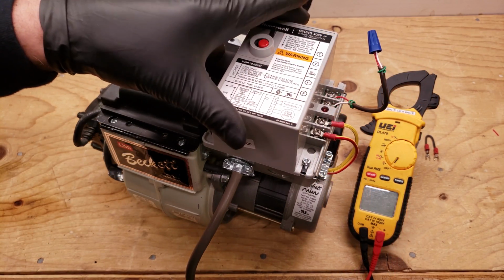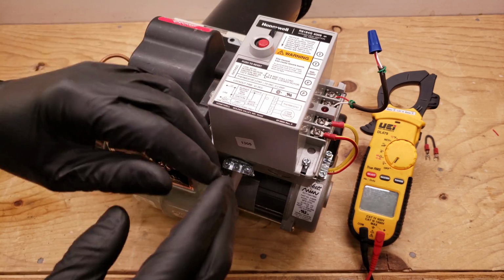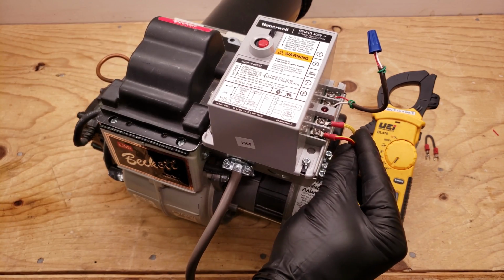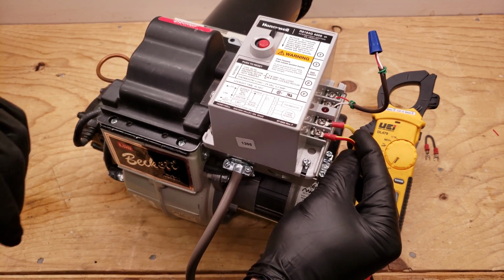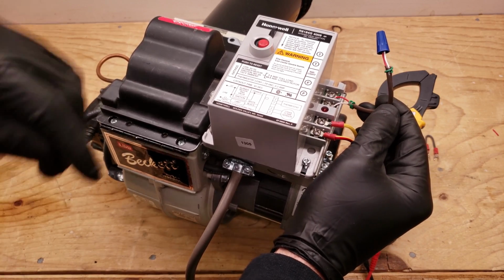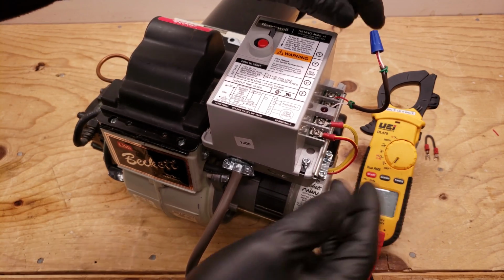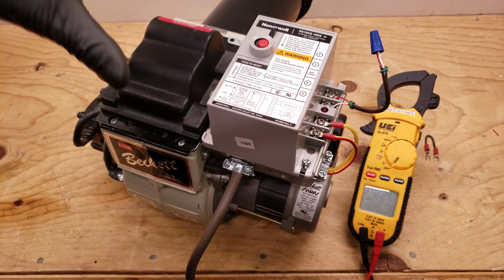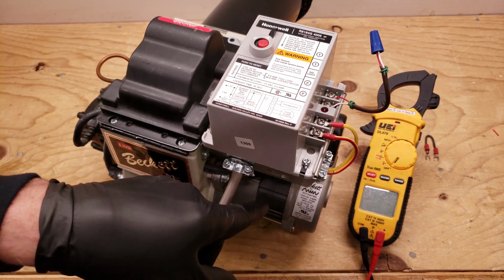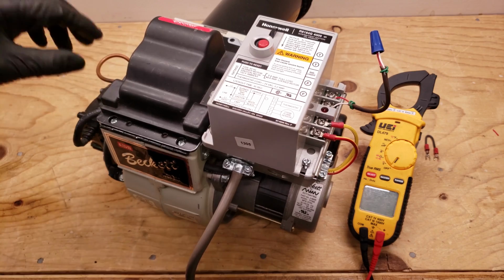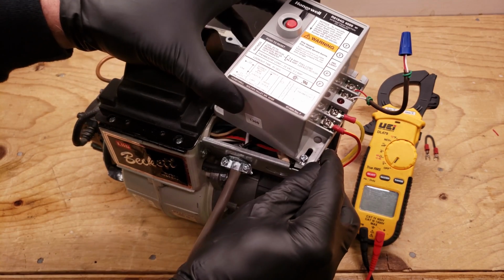Now we're going to troubleshoot the oil primary control. And this should be fairly easy because we know what the CAD cell resistance reading should be. And we also know that at the TT terminals that it needs to be connected in order for the primary control to send voltage to the transformer, the motor, and the solenoid. So what we're going to do is we'll take this off.